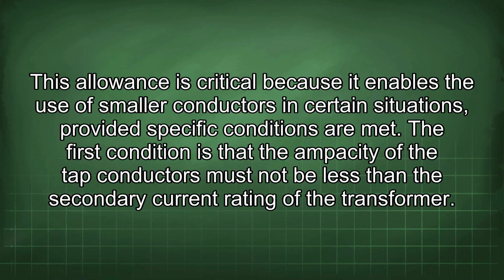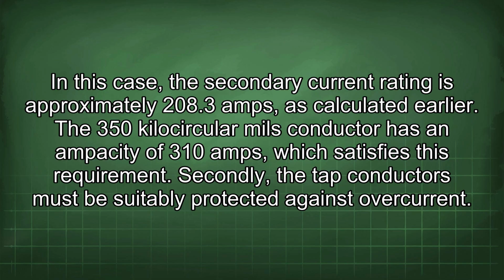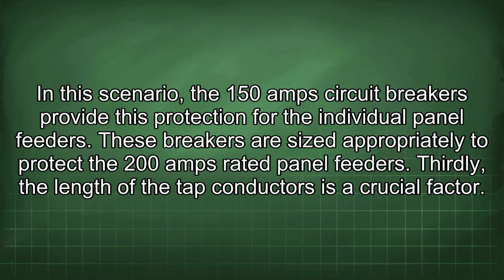The first condition is that the ampacity of the tap conductors must not be less than the secondary current rating of the transformer. In this case, the secondary current rating is approximately 208.3 amps as calculated earlier. The 350 kcmil conductor has an ampacity of 310 amps, which satisfies this requirement. Secondly, the tap conductors must be suitably protected against overcurrent. In this scenario, the 150 amp circuit breakers provide this protection for the individual panel feeders. These breakers are sized appropriately to protect the 200 amp rated panel feeders.